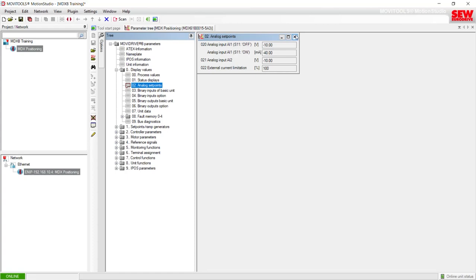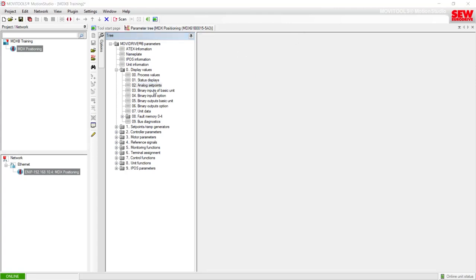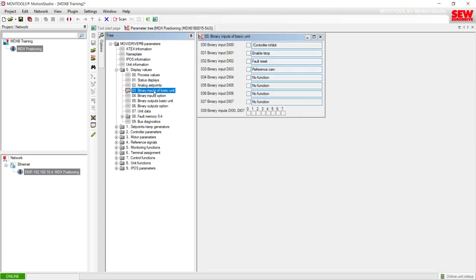The next question in lab instructions talks about item three, the binary inputs of the basic unit. I will close the analog set points and go to item three. This subgroup will show the actual status of each input. I will test digital input DI00 through digital input number seven, and we should see a checkbox come on as I go through each input to confirm the inputs are working properly.